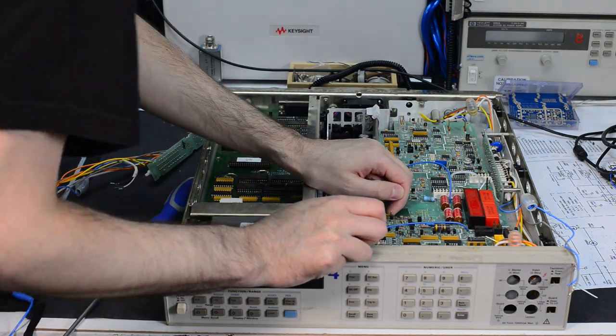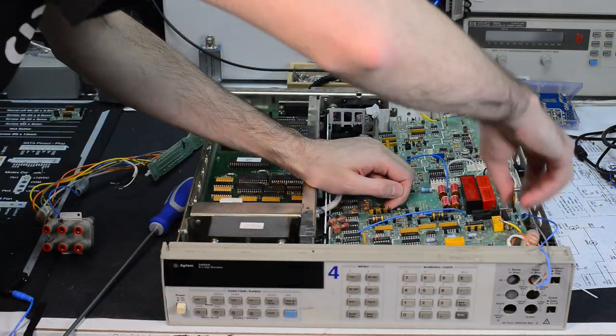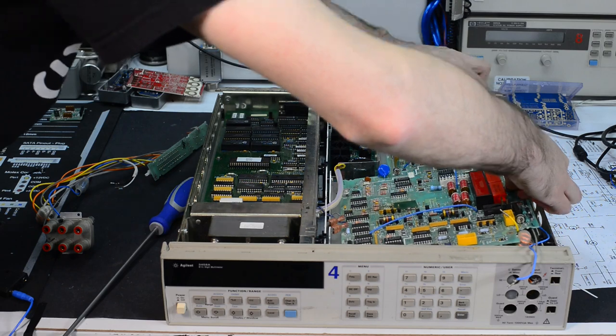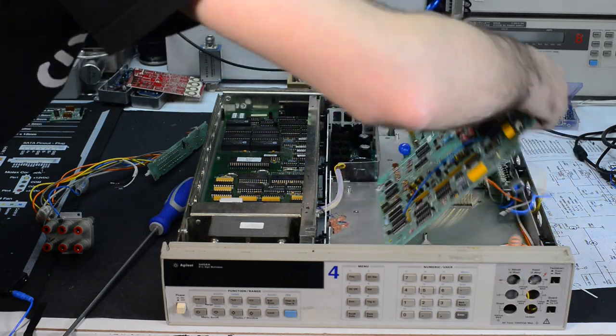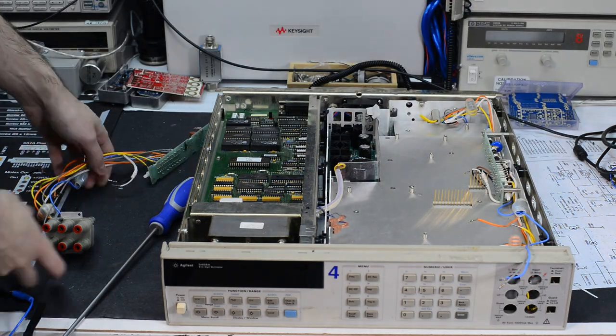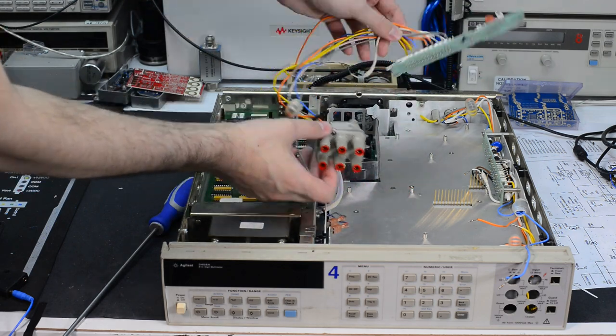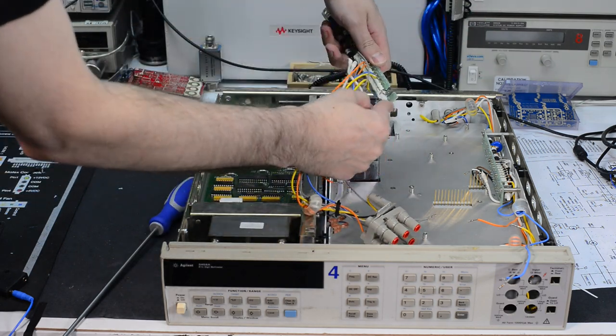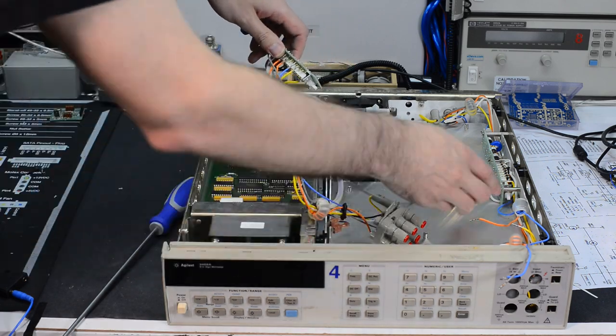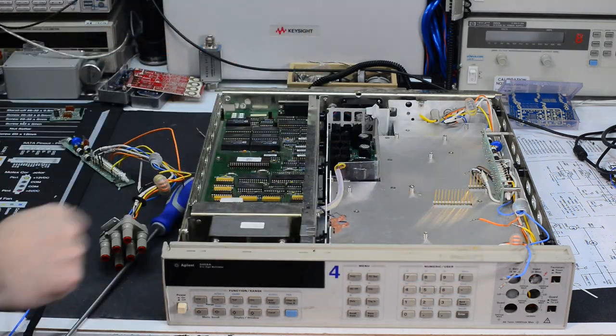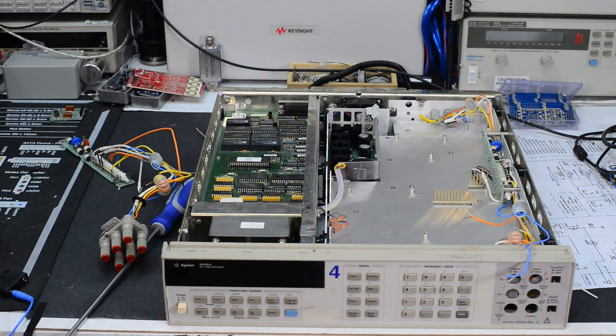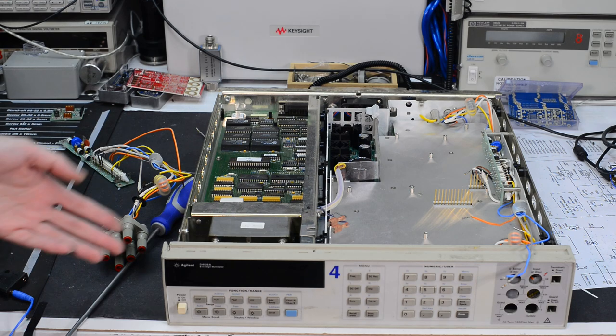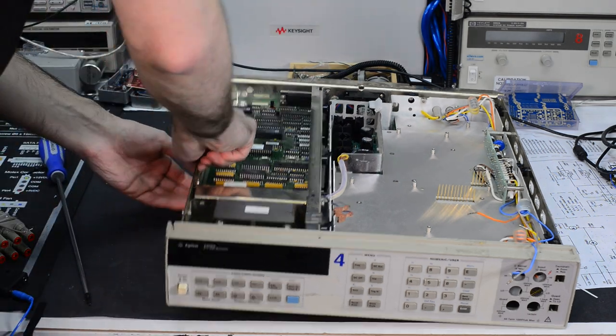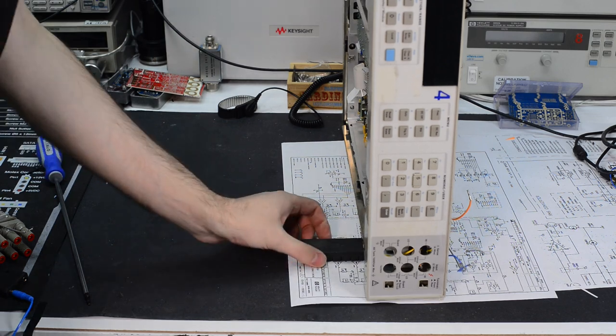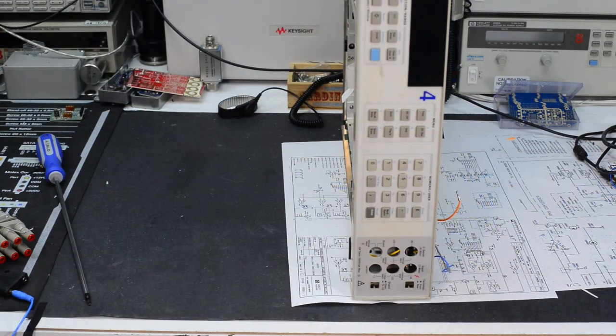So to get access to connectors that interface the front panel terminal block, I will need to remove the A10 board, which is that smaller board on the right side of the instrument. It has the front or rear terminal switch and wires connected to both front and rear terminals. To get access, I'll need to remove the front panel.